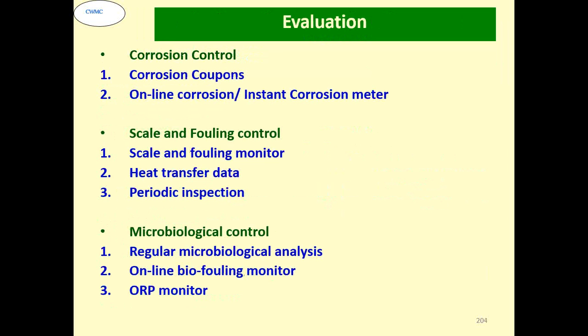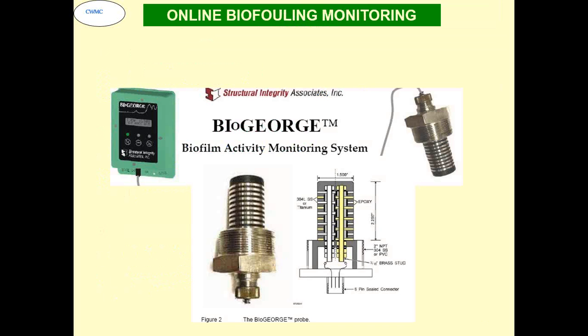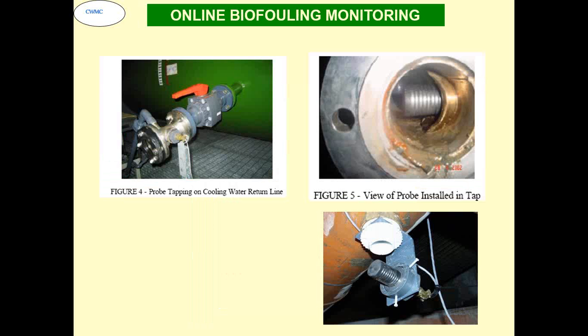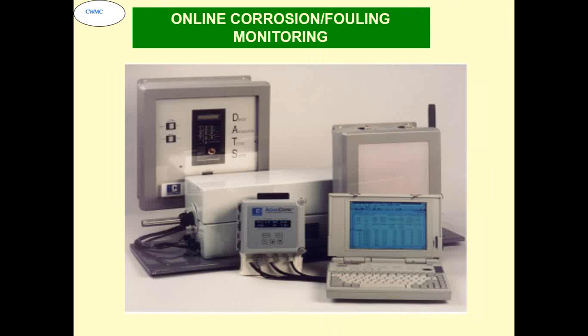Corrosion is controlled using corrosion coupons, an online corrosion instrument monitor, and a scale and fouling monitor. Now these are the typical online monitors. This is an electrochemical-based online biofouling monitor which, once installed in a system, has electrodes, as you see here. These electrodes are at a slightly higher charge. Whenever biofouling occurs, it first occurs on these and you get a change in the current, and because of that you will know there is a biofouling change. Using this system you can optimize your biocide dosing. This can be fitted directly online or can be kept open in the cooling tower also.